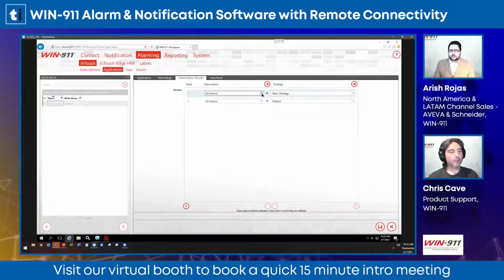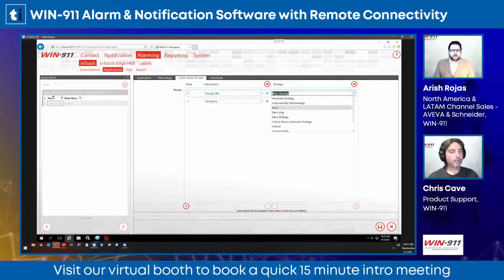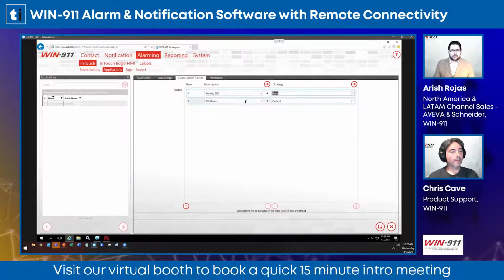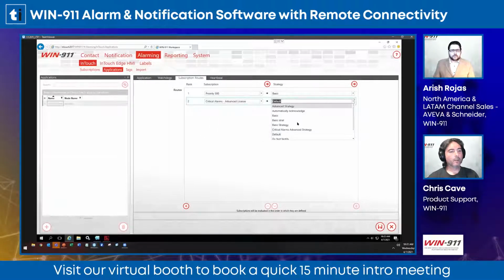But if you want different alarms to go to different people, we would set a priority subscription and set it to go to a strategy, and that strategy will trigger a call-out list. If it doesn't match this filter, it will move on to the next rank, and we could do a critical alarms catch here. This could point to a different call group, to a different group of people.